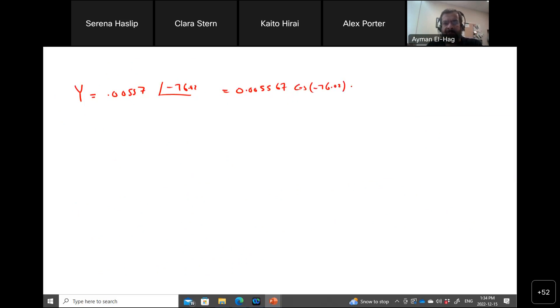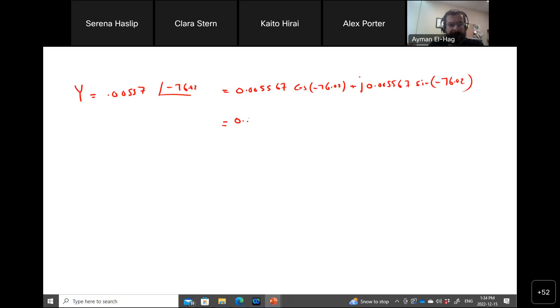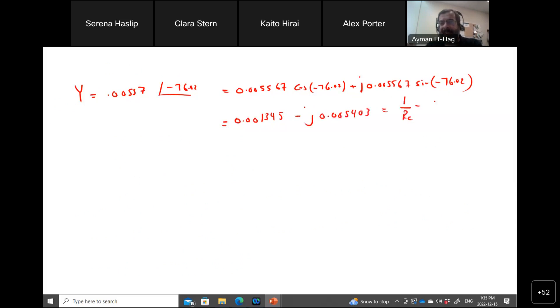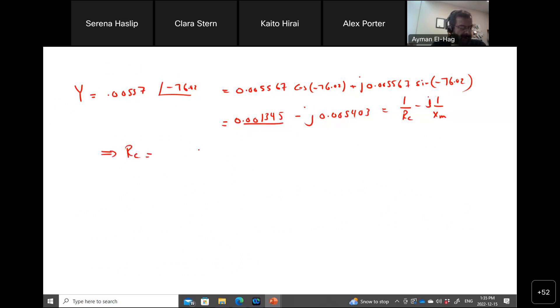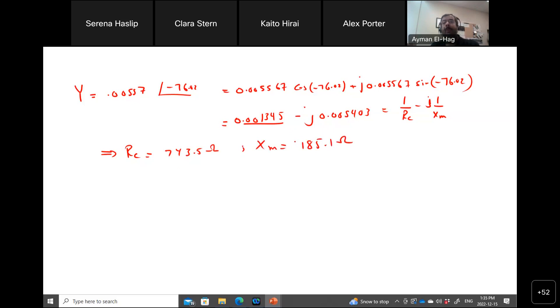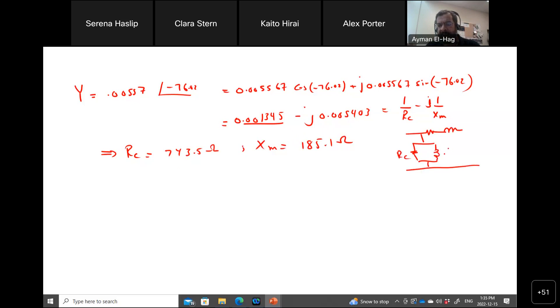Converting to rectangular form: Y equals 0.005567 times cosine(−76.02) plus j·0.005567 times sine(−76.02), which gives 0.001345 minus j·0.005403. This equals 1/Rc minus j/Xm. So Rc equals 743.5 ohms and Xm equals 185.1 ohms. The open circuit test gives you the shunt parameters of the transformer — Rc and Xm.